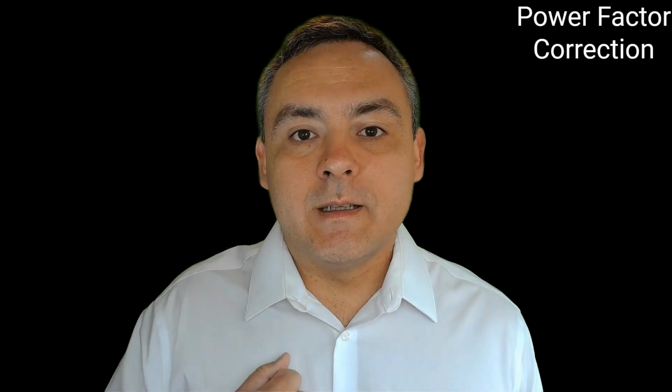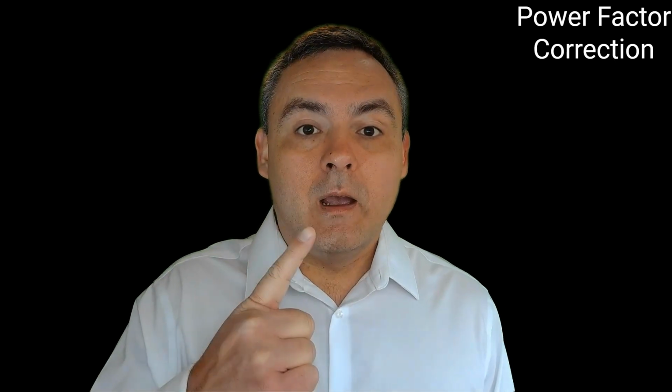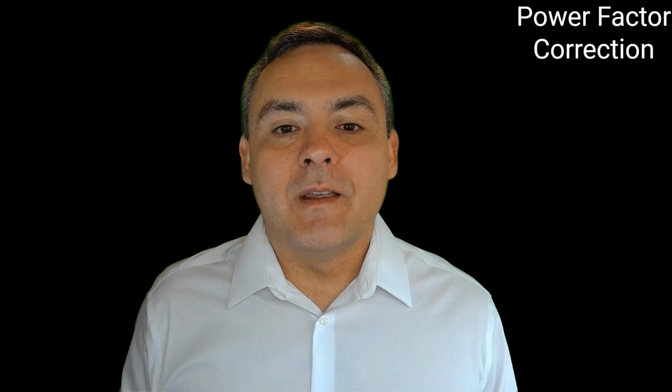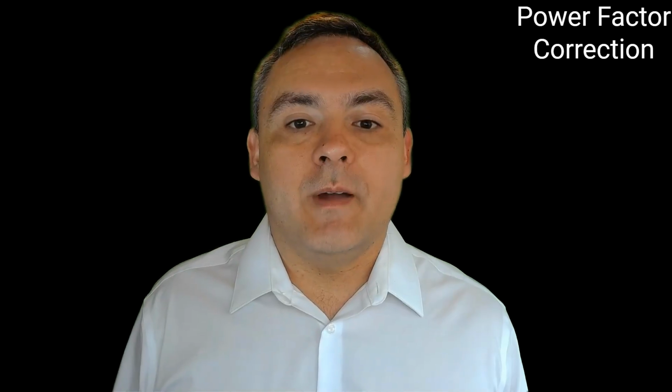I like active harmonic filters for two reasons. The first reason is they can also provide power factor correction. If you're procuring one that doesn't provide power factor correction, then buy one that does. That can be a game changer if the utility is hitting you hard for excessive power factor.